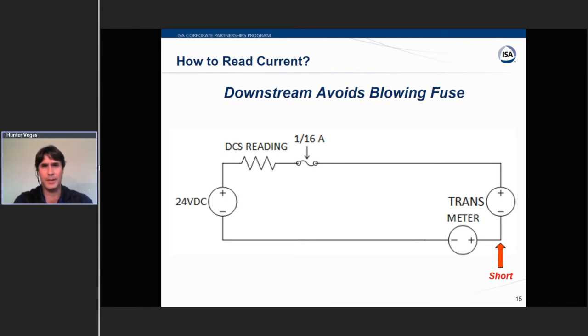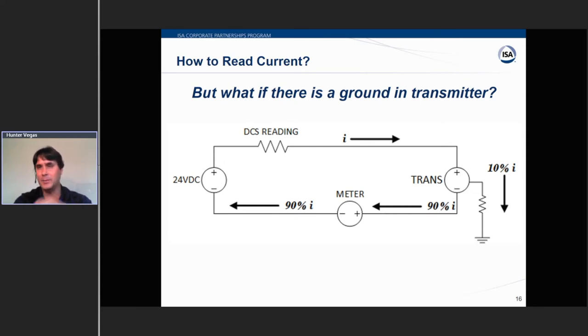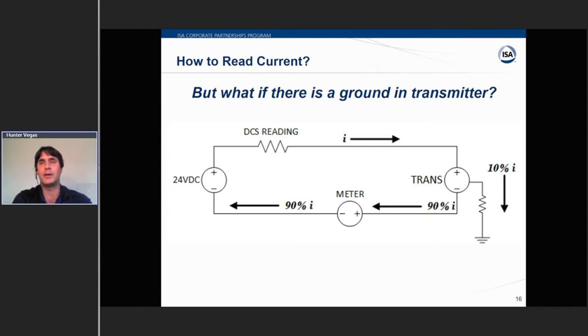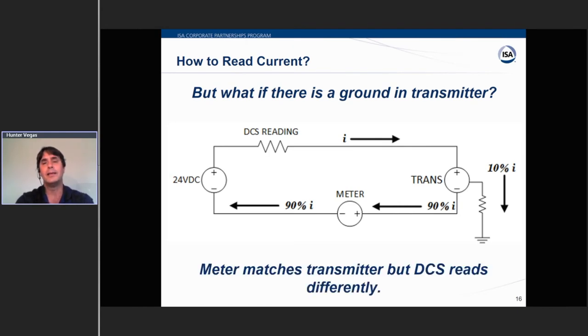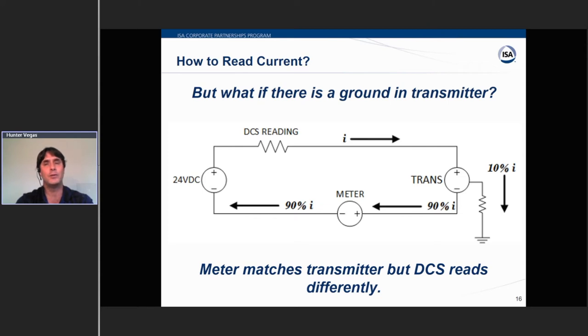But there's more to it. What happens if there's an internal ground leak in the transmitter? I've had situations where about 10% of the current leaks out before it gets to the analog circuit — 100% going in, but only 90% coming out with 10% going to ground. If you're downstream, your meter would match the transmitter output and you'd think you have a great calibration. But if you didn't cross-check with the DCS, you wouldn't know the DCS was reading something different — and the DCS reading is the one that matters.